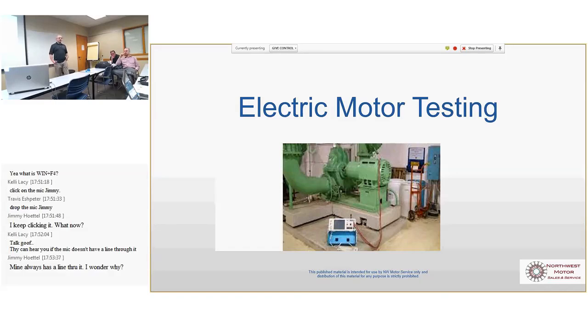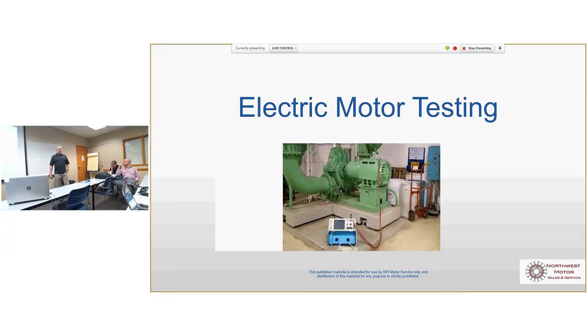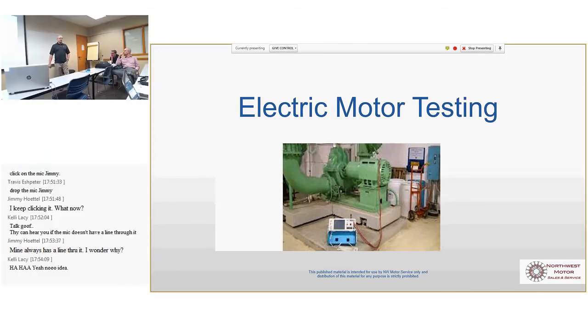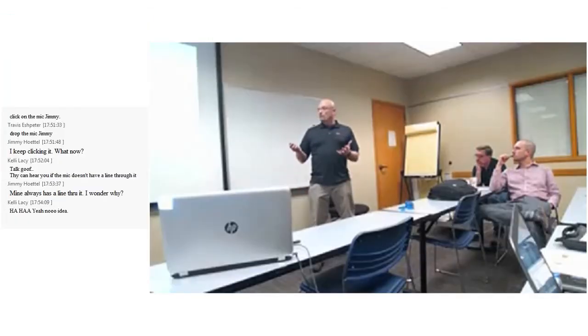wrong with the motor. But it's neat because I could hook the thing up, and then you could just gap the door, just a little bit of electrical compartment, and I shut it and walk away from it, and it just records until we come back a couple days later, and you can see all the events that happened, and we could check everything: power factor, voltage, over under voltage, current, harmonics, torque, speed, just about anything you think of. So that's pretty cool too. The online testing is a really good troubleshooting tool. But this is a very strong tool for giving you the condition of the insulation, winding, stuff like that.